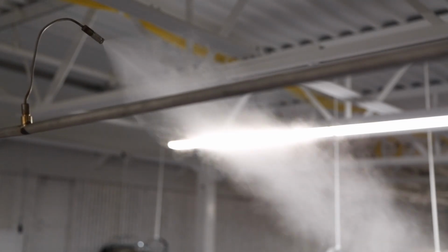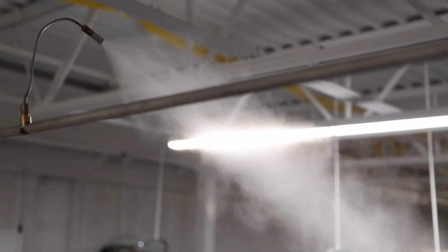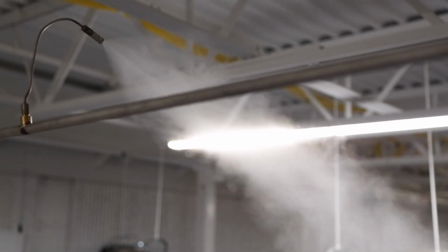When we're looking at different adiabatic solutions, what are ones that we should consider, especially if we're thinking about putting adiabatic humidification into an AHU? And what might be the best fit for that? Well, there's a couple different ways. We said it was water droplets, and it's a matter of how do we get the water droplets? You can pressurize the water really high and send it through a really small nozzle, causing it to shatter into a lot of small particles. So a high pressure type system.